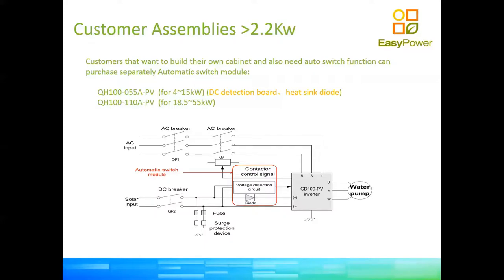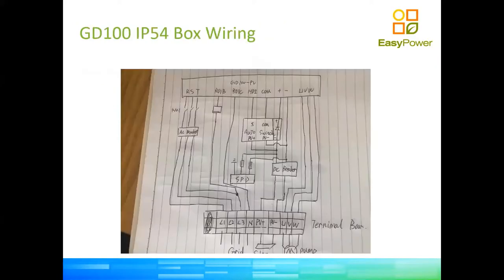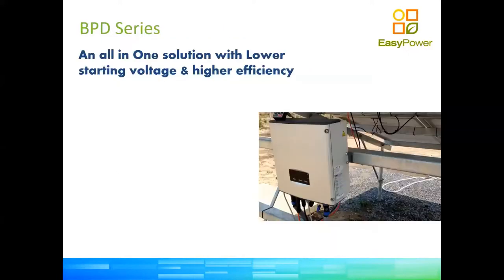This is the same setup shown as a single-line diagram. The detection board for switching between solar and grid comes in two models depending on pump inverter size: the most common is the QH100-055A-PV, and there is a bigger version for inverters from 18 kilowatts upward. The GD100 is highly customizable: you decide whether to include the PV booster, the auto switch, or have everything wired together in an IP54 enclosure.